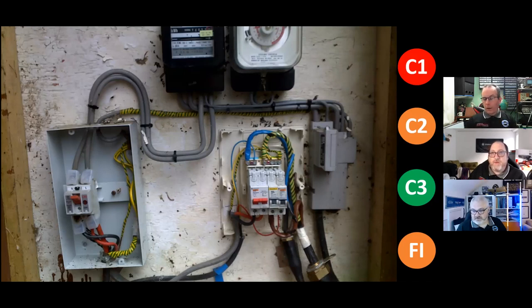Okay, let's end that one and share that one. Right, C1, 98% of you bang on. I agree with the C3s as well, by the way, and the C2s, because it's just crap and it needs improving. Again, this is where the problems are. So yeah, it's C1, you got C2 for the armour's not connected, and all the codes basically. So yeah, there are many observations in one picture there. So maybe people watching it can use it as a practice method, see how many codes you can pull out of this. How many regulations does this one picture give you? It's a good way of writing up your reports.